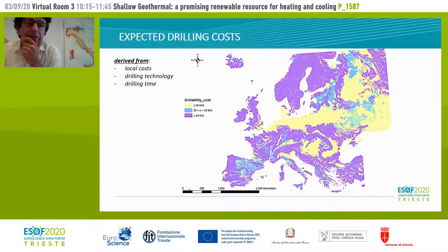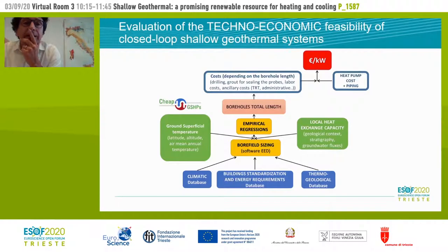In this slide you can see the flow map of the work that permits us to evaluate all the main characteristics of the plant, such as the type of drilling machine, drilling methods, the total borehole lengths, and the euro per kilowatt for the installation of the borehole heat exchanger. This value is assigned to heat pump cost and piping.